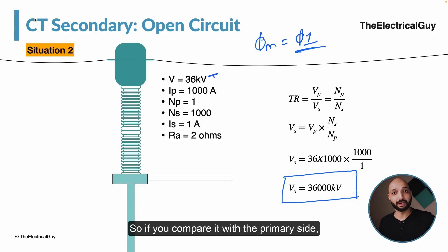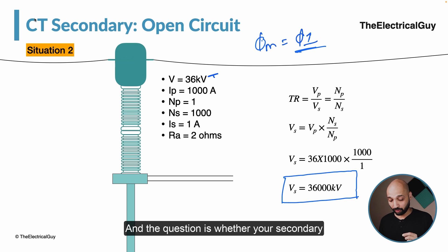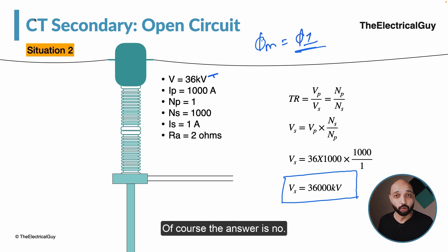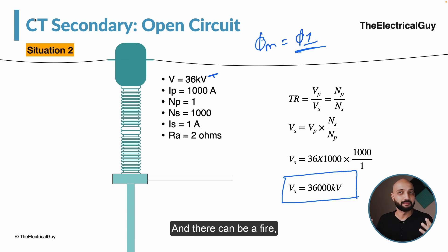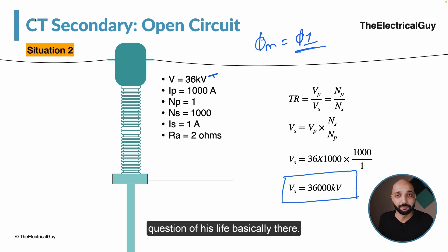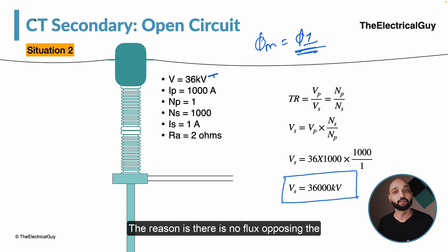The question is whether the secondary of the current transformer is designed to handle this huge voltage. Of course the answer is no. This huge voltage puts enormous pressure on the insulation of the secondary, which will eventually fail. There can be a fire, there can be a big blast, and if somebody is working near it, there is a serious risk to life. The reason is there is no flux opposing the flux produced by i1.